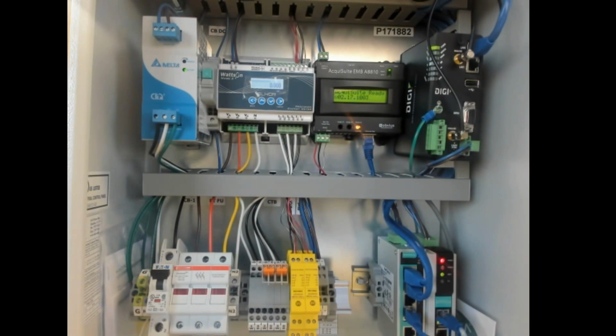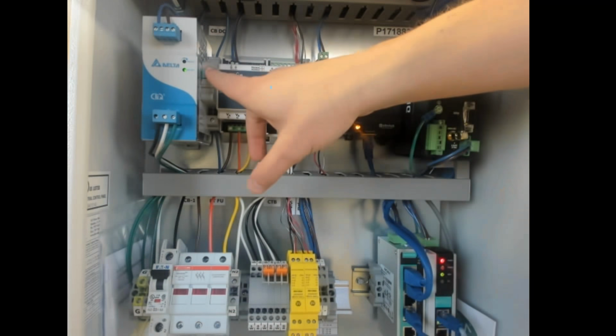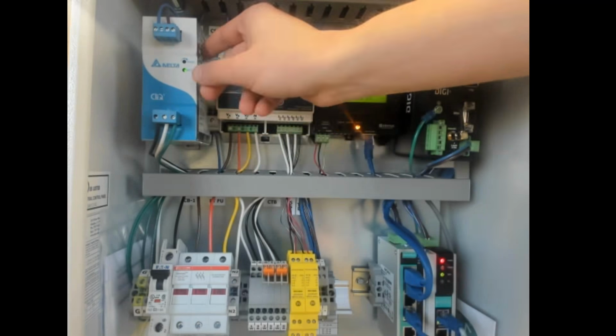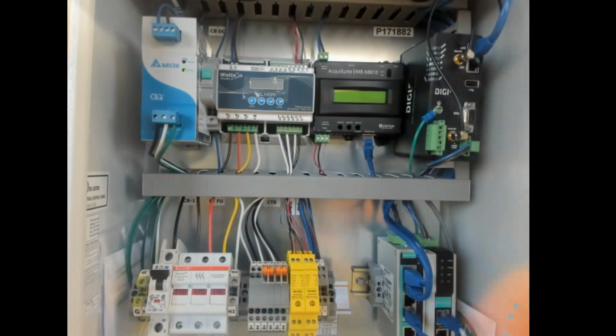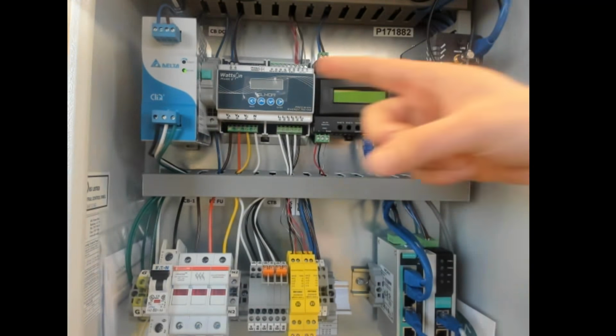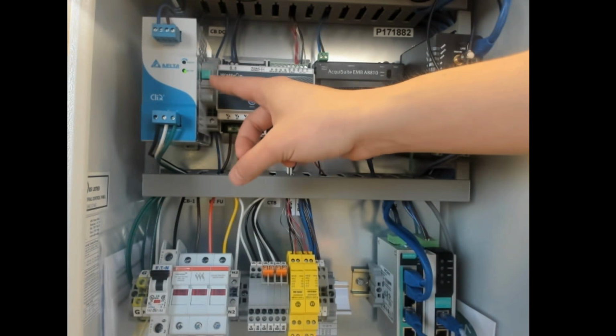Now there's another step involved, especially when you're taking this unit out of the panel and hooking it up for the first time. There's actually a DC breaker in the design now, and the reason for that is because we have a lot more power going into this panel than before. The sales guys will probably benefit from that eventually when we can say we can add more devices externally fairly safely, but because of the higher amperage or power, we actually need to add a DC breaker.